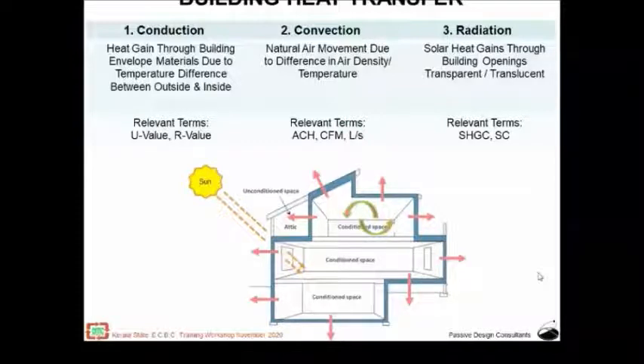Hence it is important that when we design our walls and roof, we design them with insulation, so that the amount of heat travel to the inside is reduced or limited or restricted by using thermal insulation materials or building construction materials, which can reduce that heat gain through conduction.